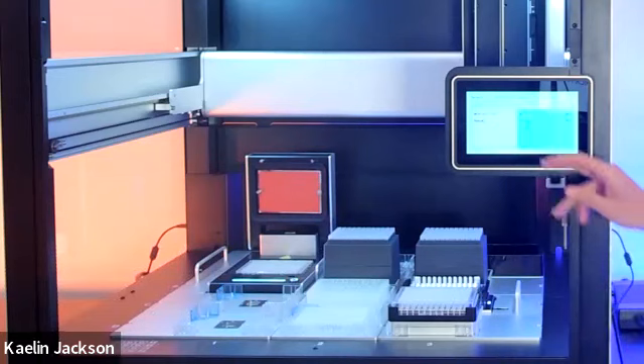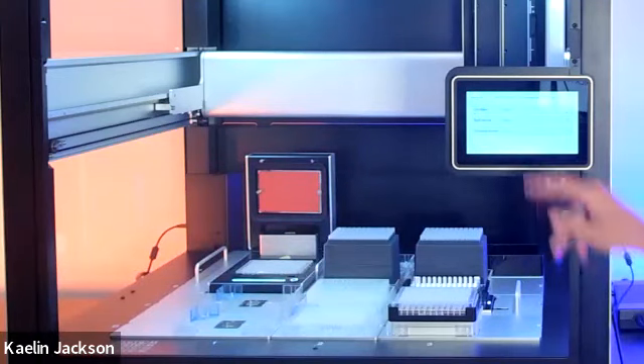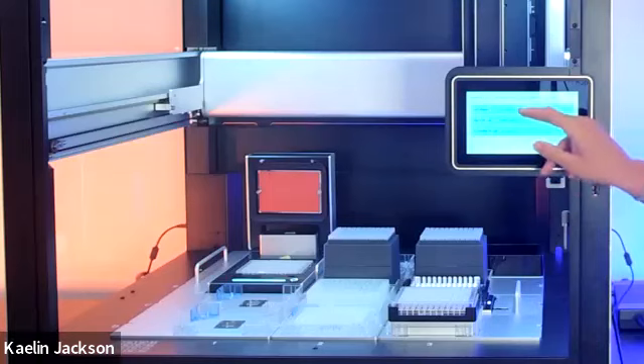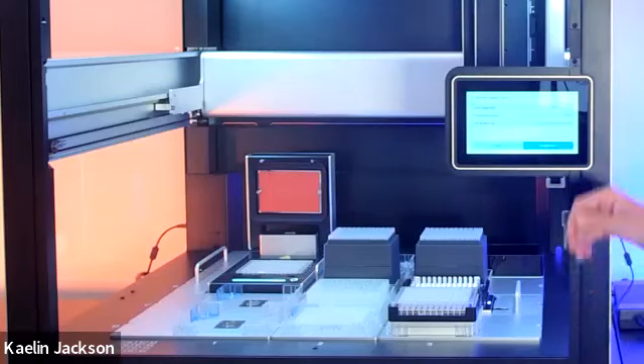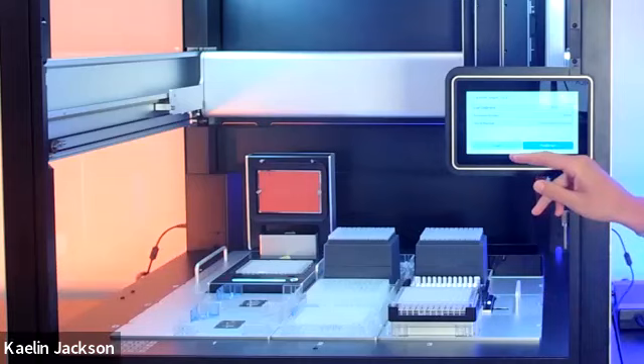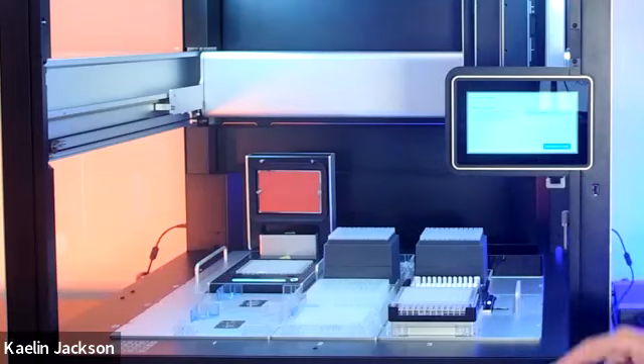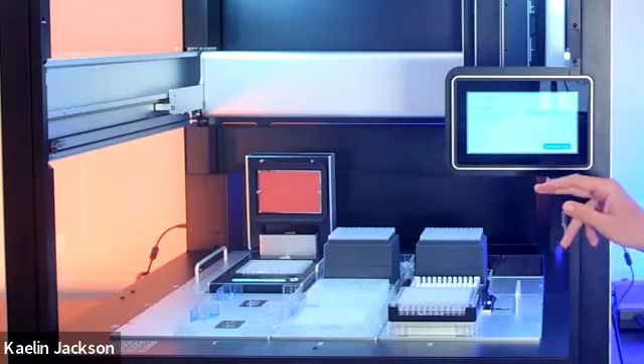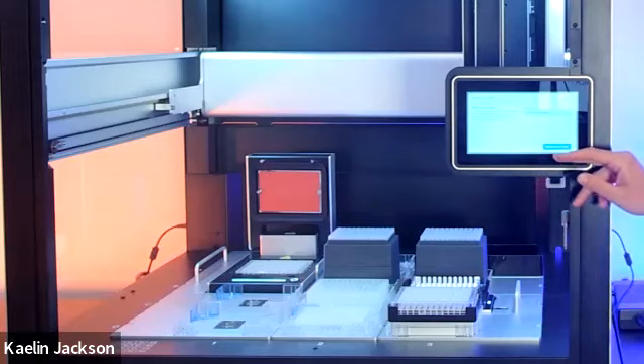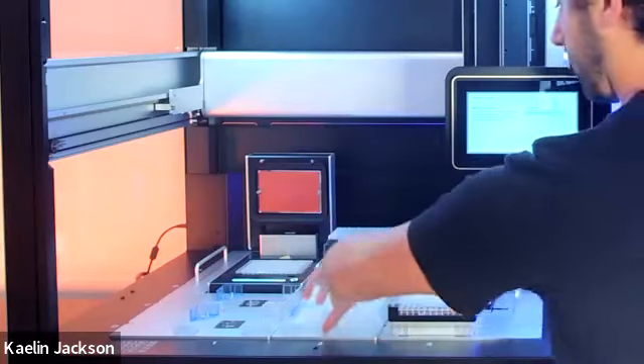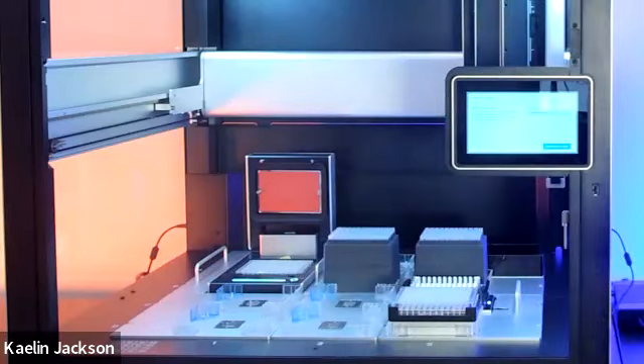So on the on-device display here, I'm just going to navigate to our Instruments tab. I'm going to select our left mount, and let's say that we'd like to detach our P1000 single channel pipette. I'll simply select Detach. I'll be notified that I require a 2.5 millimeter hex screwdriver, which ships with the robot. It also lets me know that I'll need to move the labware off of the working area of the deck, which in this case is slots 2 and 5. So I'm just going to replace my plates there and grab my driver. I'll select to move the gantry to the front of the robot.